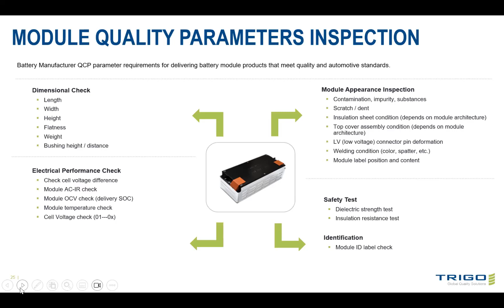Here also we have the safety tests, two key ones: the dielectric strength test and the insulation resistance test. Those are done by applying a high voltage peak and looking at the behavior of the battery, both the insulation resistance and the dielectric strength.